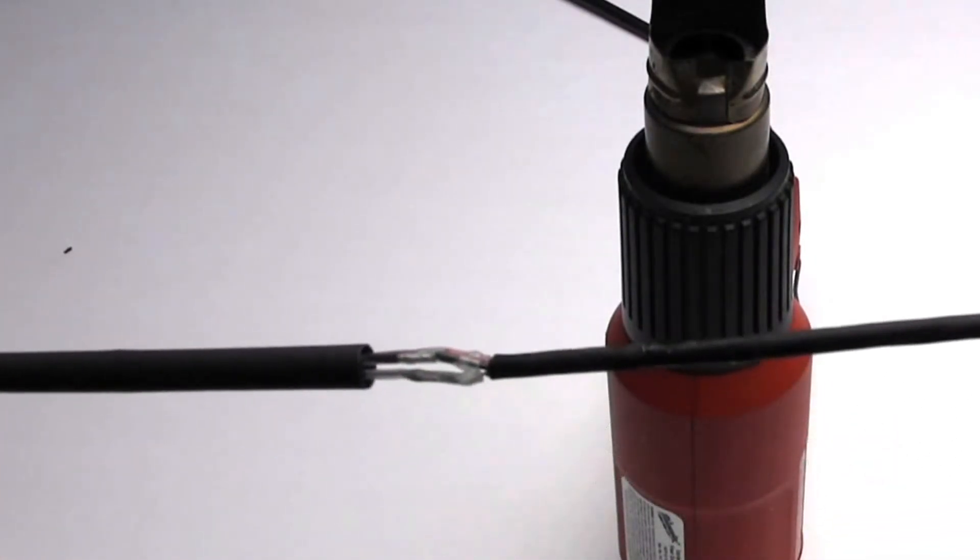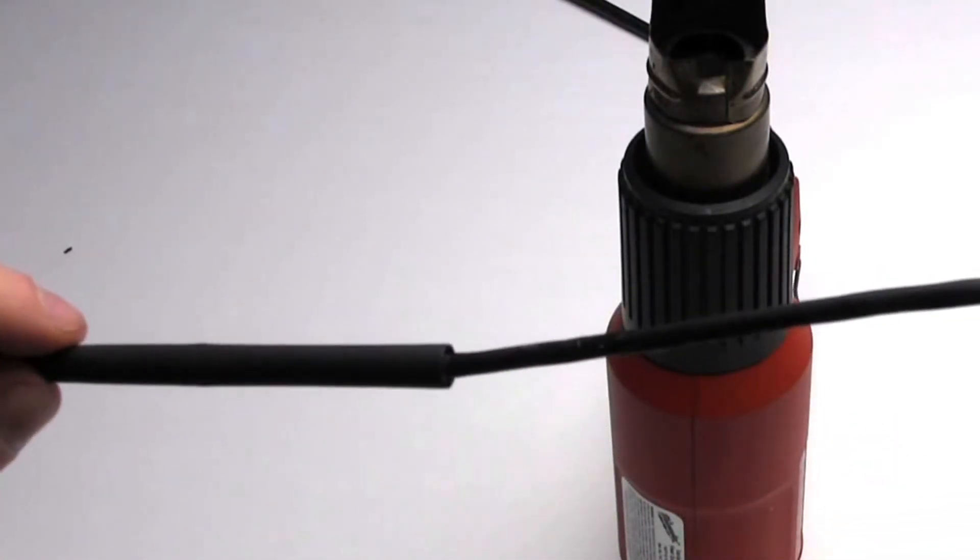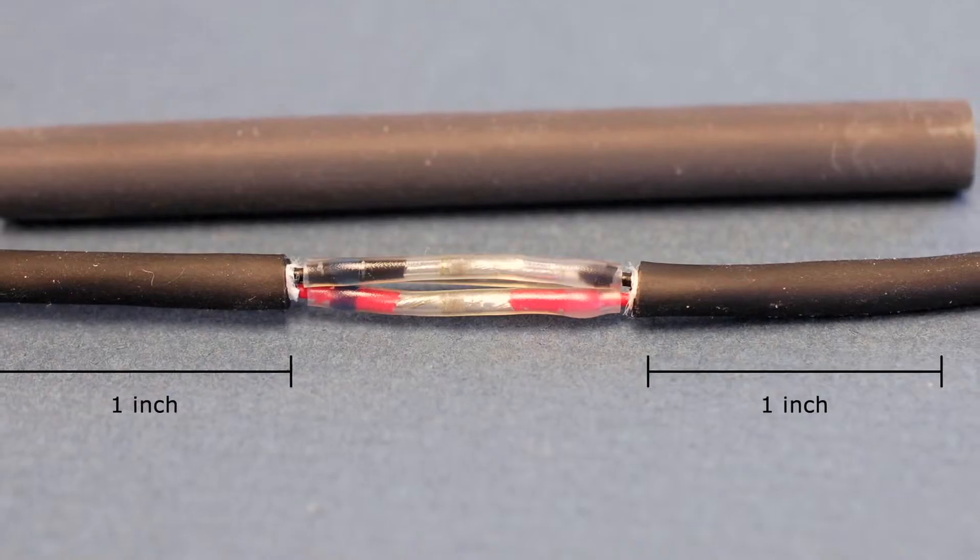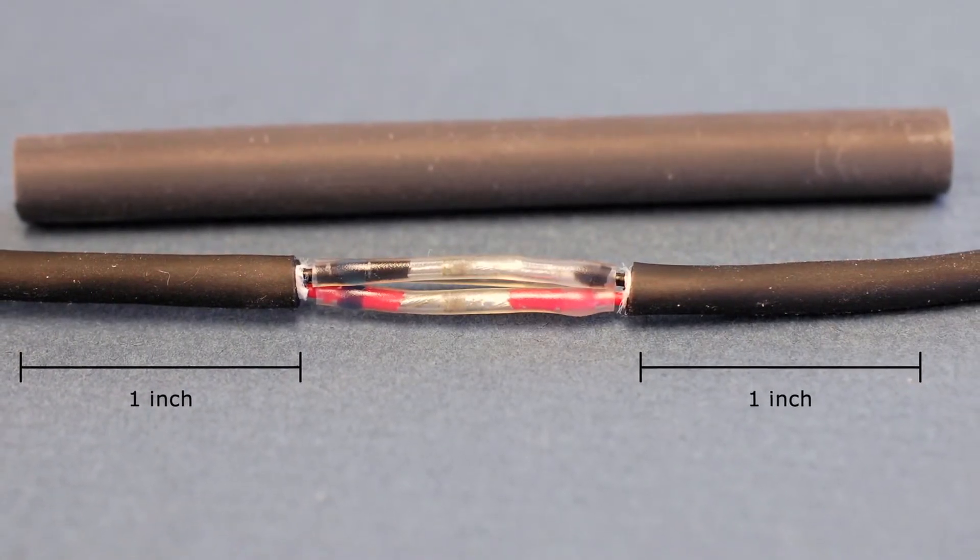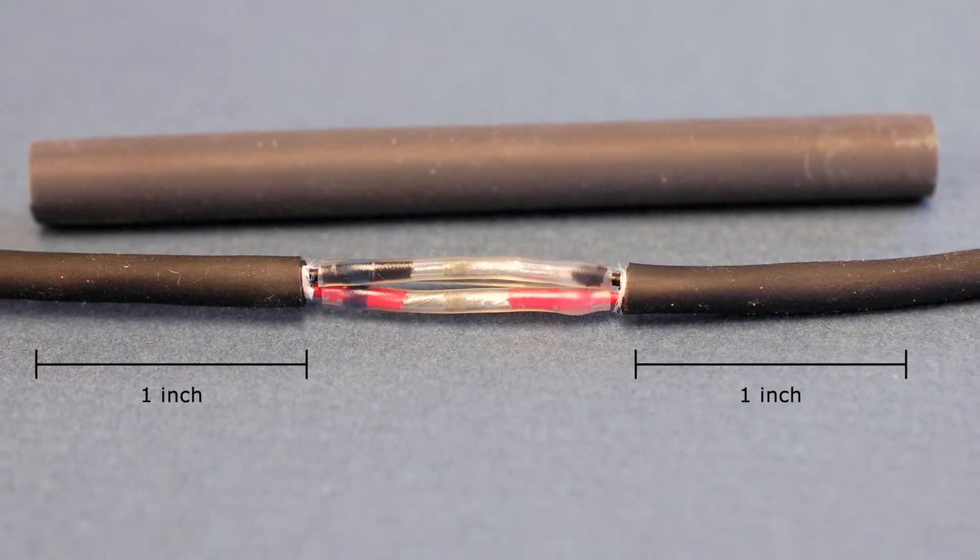For step six, slide the polyolefin adhesive lined heat shrink over the junction of the wires, this will seal the splice from the elements. Allow an extra one inch of coverage by the heat shrink on the outer jacket of cable to ensure a good seal.